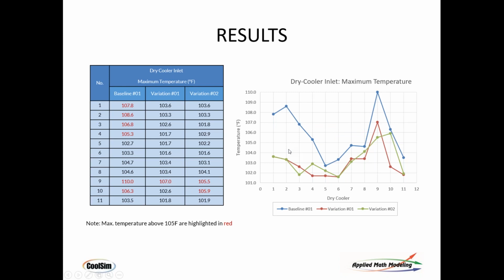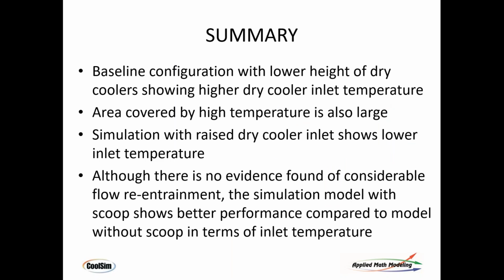And you can do more of that. So you can plot them. We have the analytics. The post-processing on these runs allows you to get very fine detail on the analytics and show you temperatures, very, very finely controlled temperature gradients. So in this case, we found that the most important thing was getting those dry coolers up in the air, and the temperature coverage was quite high. So getting them up in the air made things better.